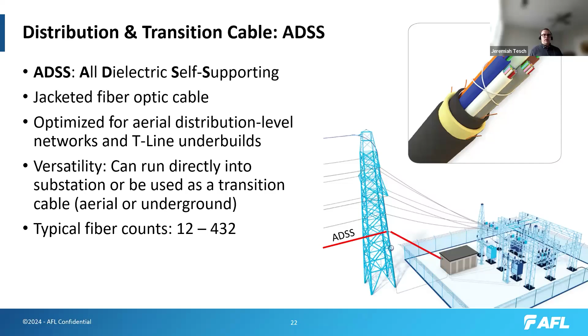Just to highlight a few construction elements, typically ADSS is stranded around a central strength member or FRP rod - a fiberglass rod that's fairly flexible. This provides a stranding member, kind of like on the stranded OPGW. We wrap or strand fiber optic buffer tubes around this to keep the fibers contained, at a certain number of positions to maintain a circular profile.